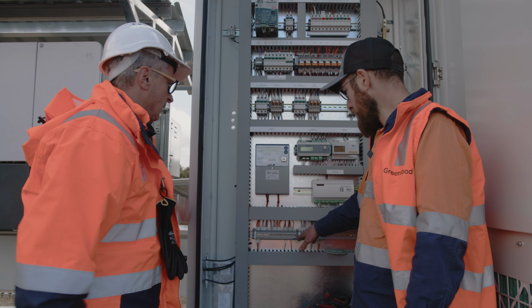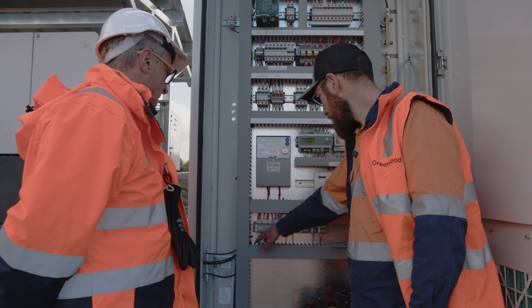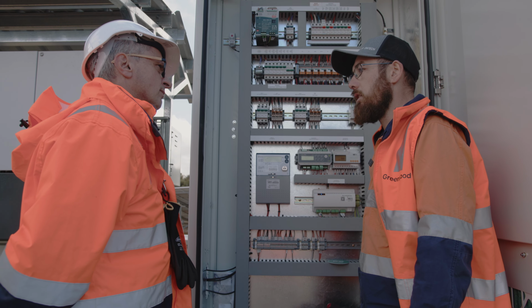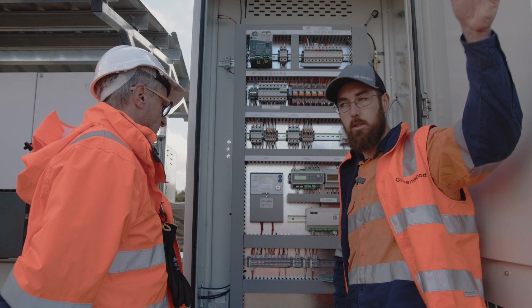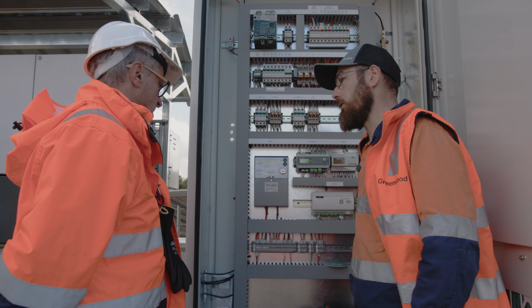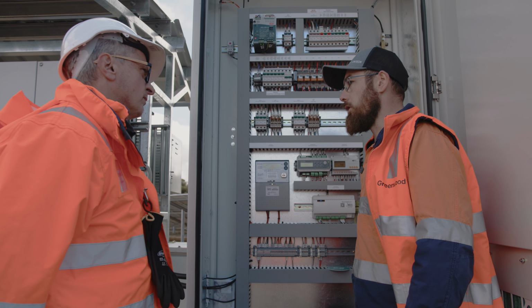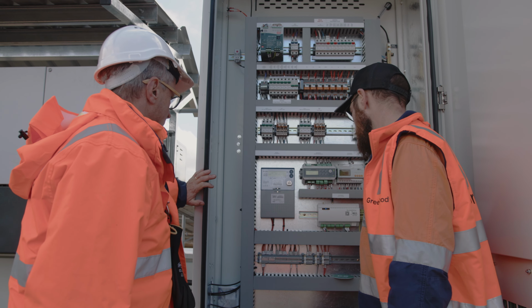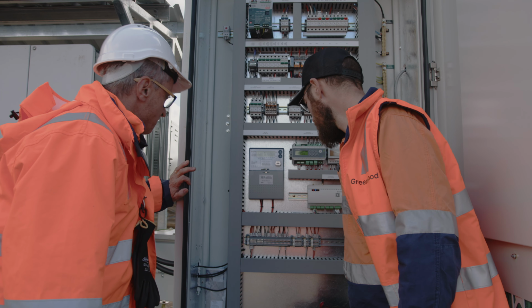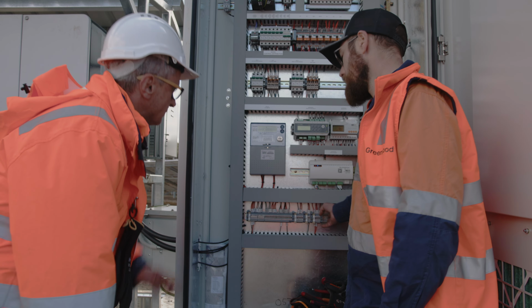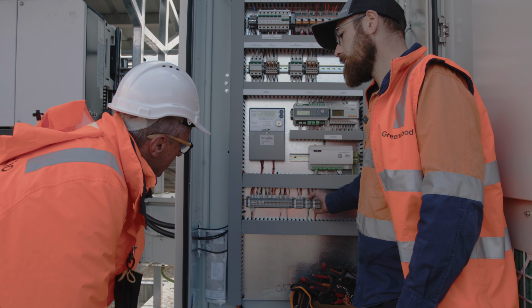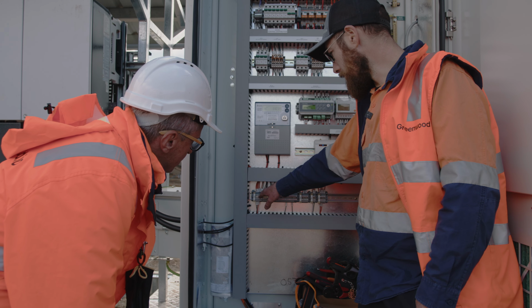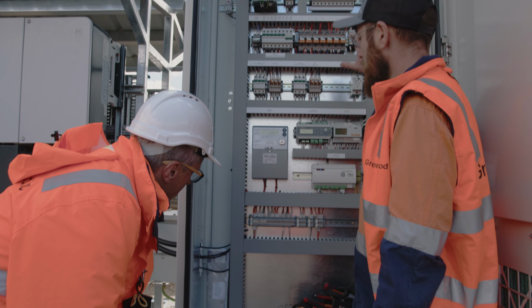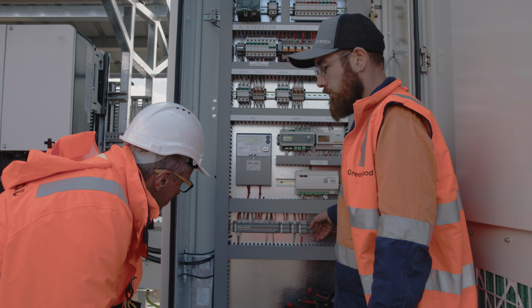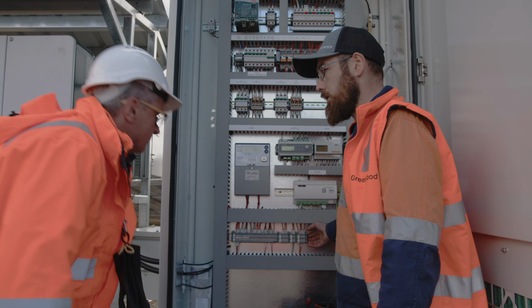Specifically, these cables here are connected back to the high voltage RMU over in the distance, so that's where our communications for the oil temperature and oil pressure are going to be sent back out from this board. Typically when you see a connection block like this at the bottom of the board, it's for connecting external equipment, giving you all the terminal points for your different equipment above, at a readily accessible location for testing and connection to any devices.